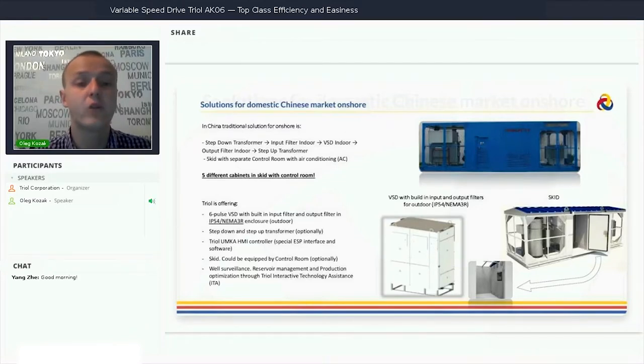Let's start with the onshore solution for the Chinese market. Based on information we have, the traditional solution is an indoor VSD. This is the skid you see in blue on the screen. It includes a step-down transformer, an input filter to reduce harmonics, an indoor VSD, usually IP20 or IP21, 6 or 12 pulse, an output filter, a separate cabinet, and a step-up transformer.